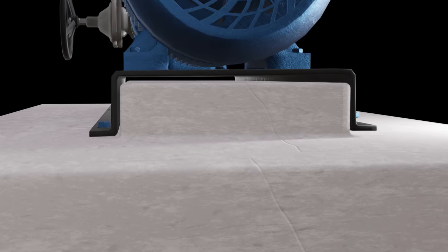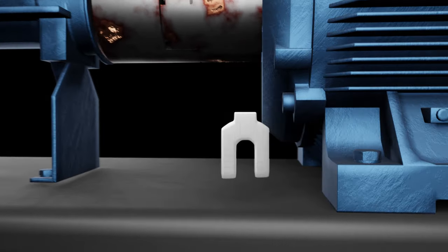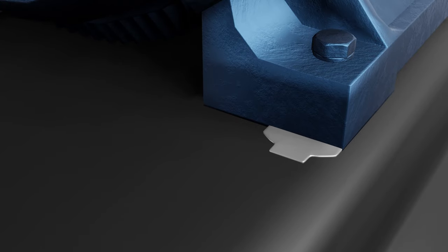Concrete bases can shrink, leading to gaps under the frame. Shims should be installed under the motor feet. They should be pulled back slightly, so the bolt's threads don't bend the shim when they are tightened.